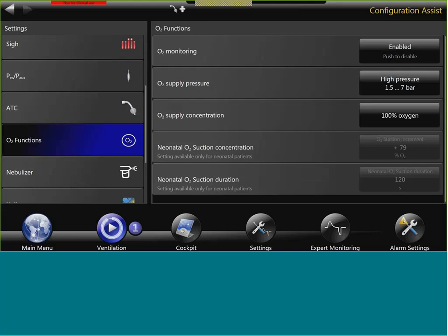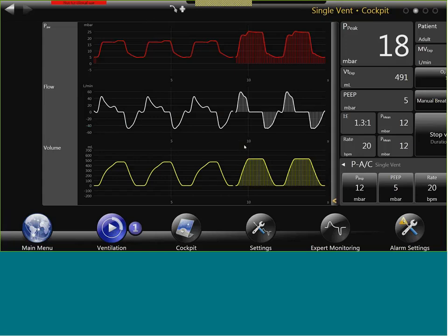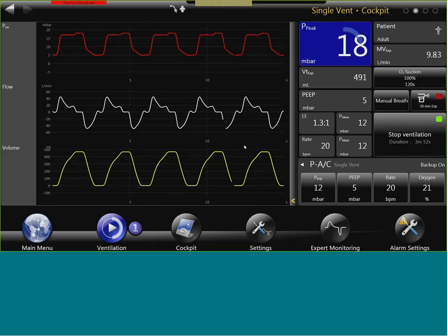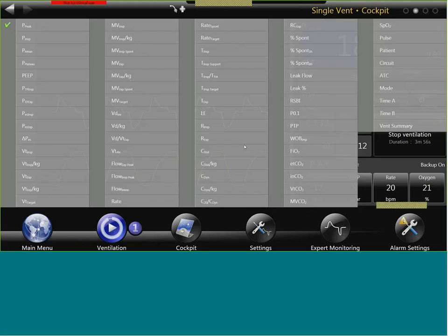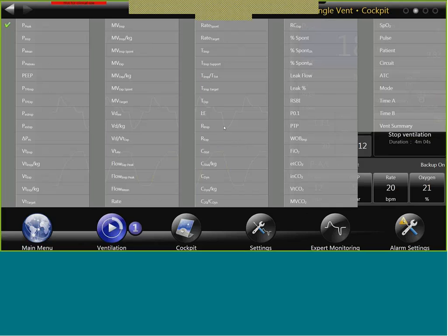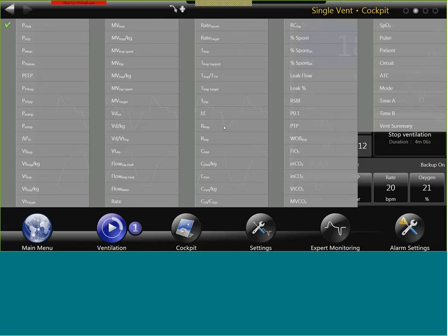So there's the opportunity that you say, okay, I will totally disable the O2 monitoring. So that means I have an alternative means of oxygen monitoring, but there is no oxygen measurement coming from the bellavista anymore. And this means that the oxygen mixer is looking at a relation between air and oxygen, but it's not connected anymore.